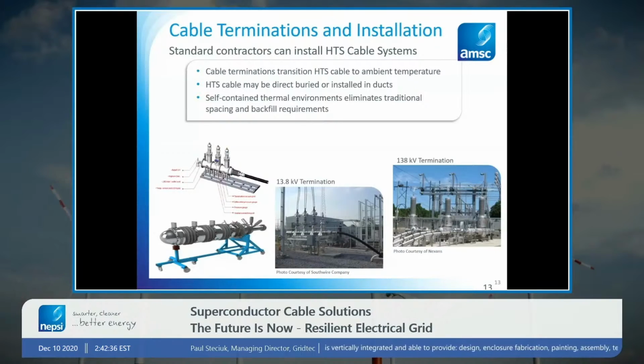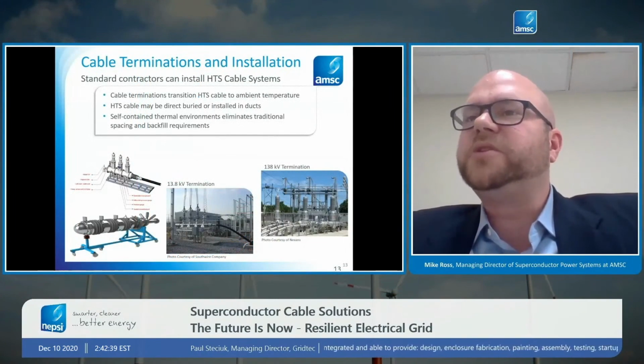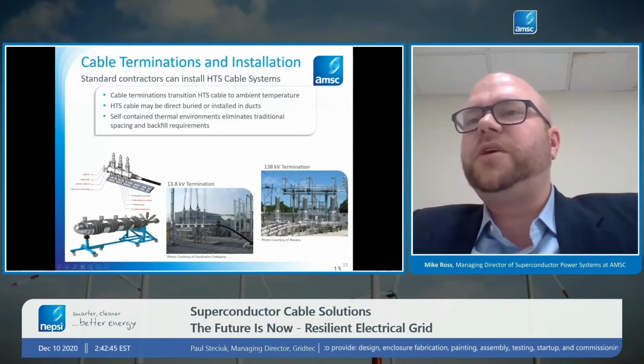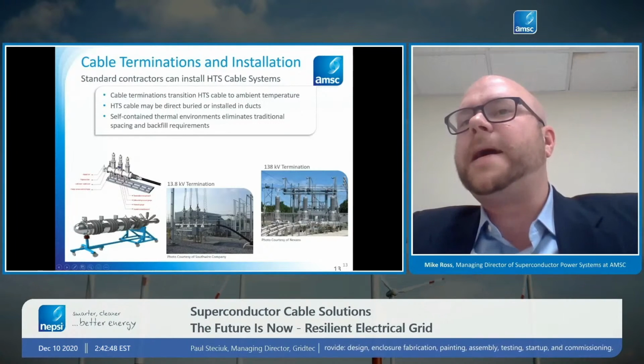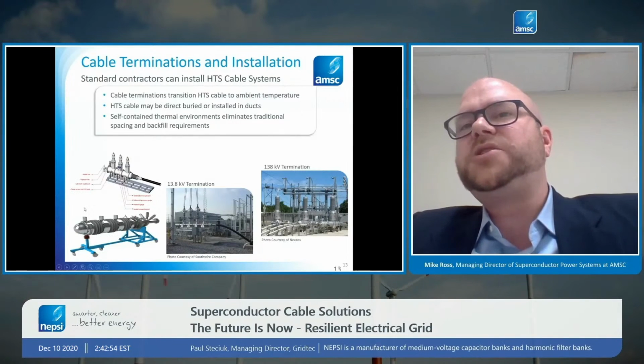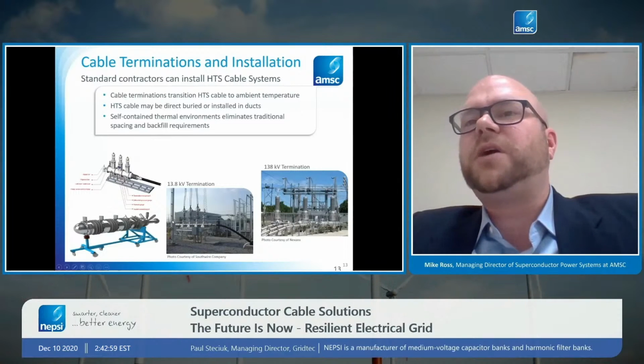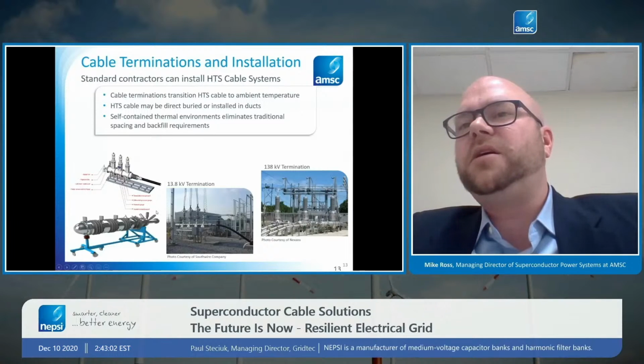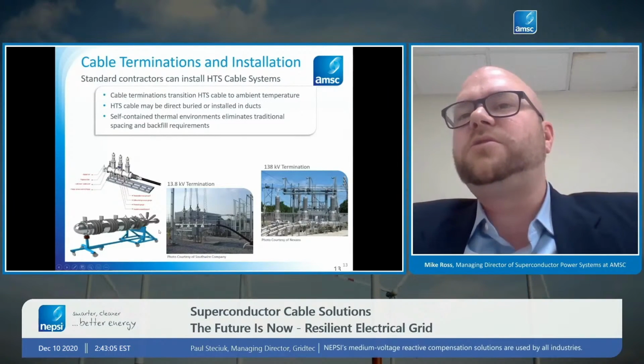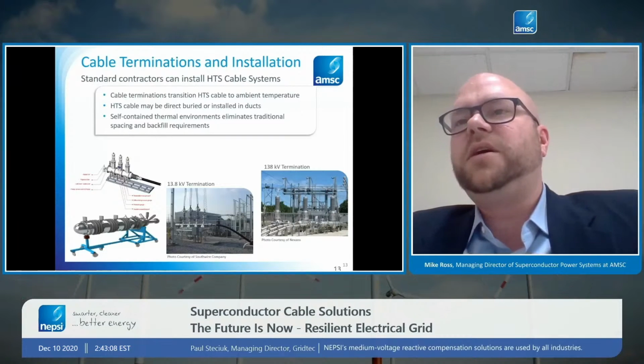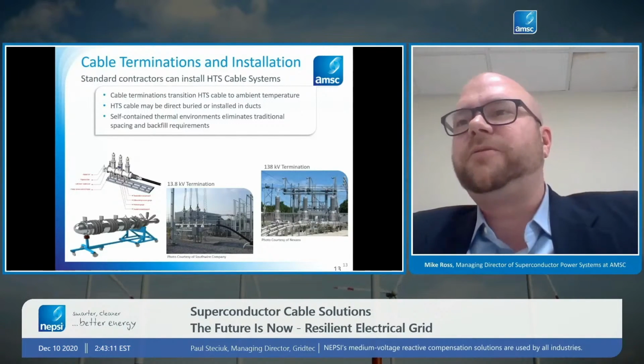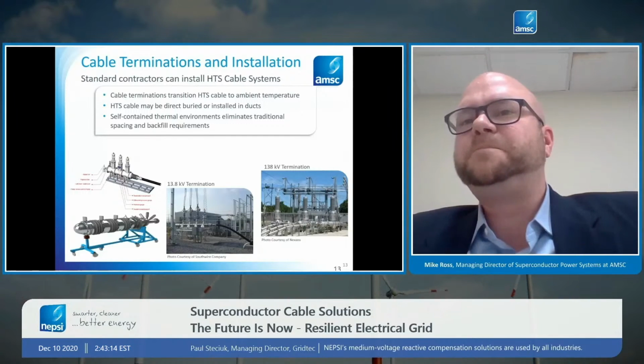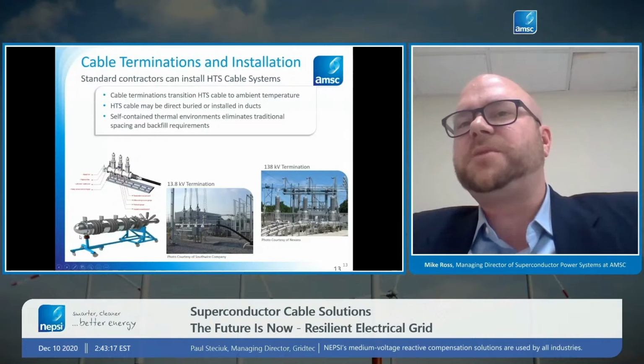So this was the original prototype. We learned that this was a bit large. We were able to demonstrate the technology, which was fantastic. It's a bit large for practical applications. So over the years, we've now developed a much more compact, modern termination, which is what we're seeing here. So in this termination, again, you have phase A, phase B, and phase C coming into the termination, and the power cable comes out the end. This is designed to be installed in metal-clad switchgear or typical utility cabinets, and therefore it's very compact and very easy to install. This is for distribution voltages up to 36 kV.